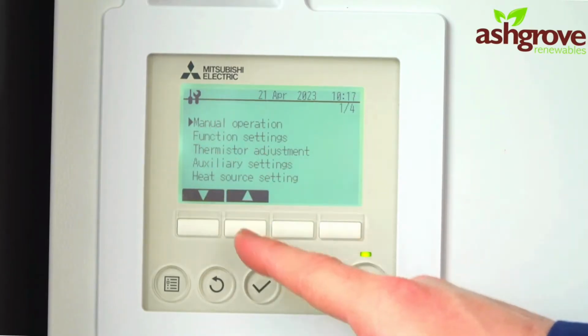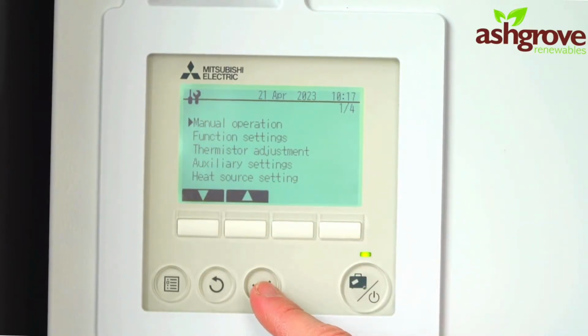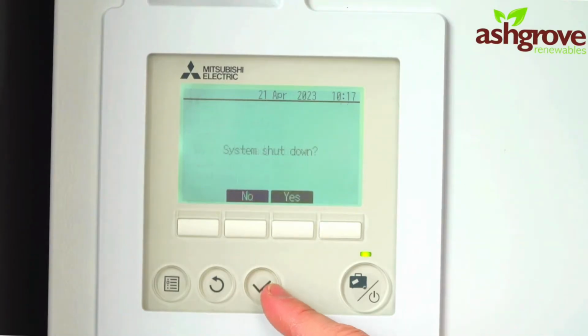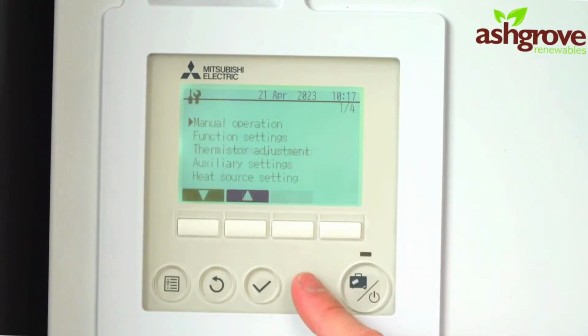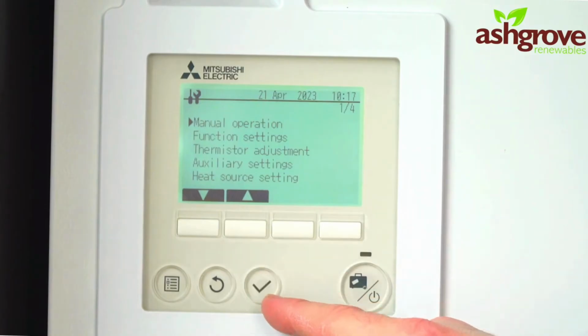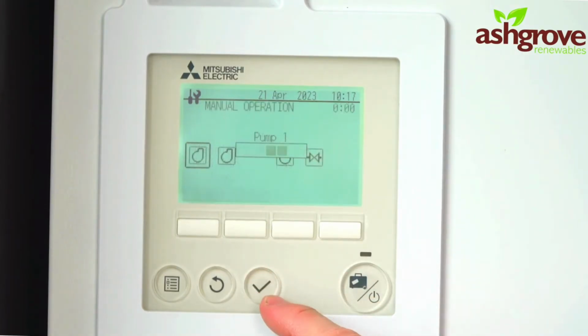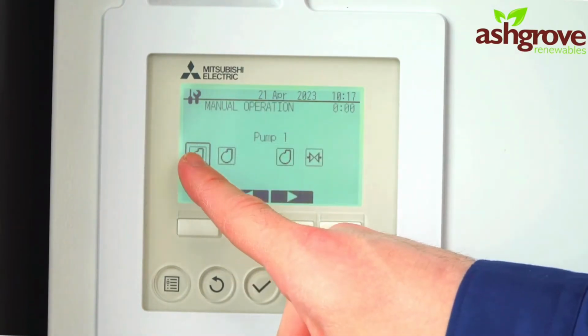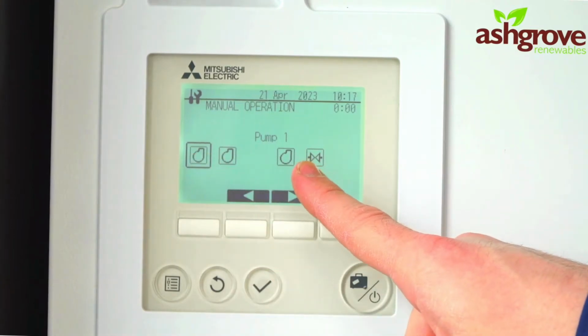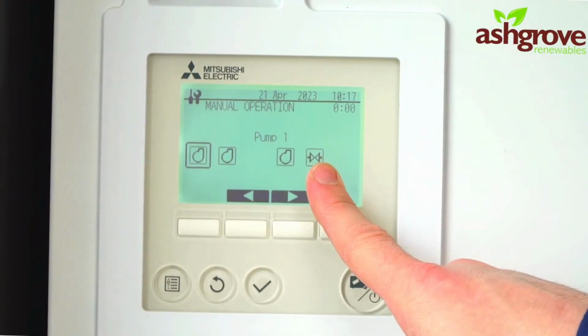It will start loading the service menu. Now we can go into manual operation, and it's going to ask me to shut down the system. We are going to shut it down. System shut down, yes. Now we're back at manual test. Press the tick button. We have 3 pumps in this scenario and a 3-port valve.